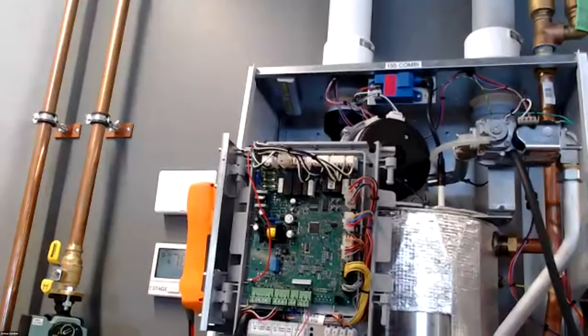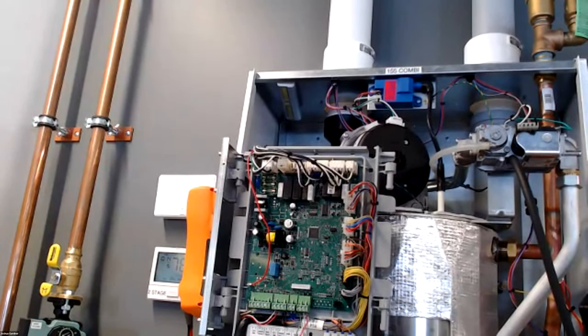And then on PVC, every 90 is 5 feet and every 45 is 3 feet. And I recommend using long sweep 90s. You can use regular 90s, but anything we can do to relieve the restriction is best. With CPVC, with poly, every 90 is 10 feet and every 45 is 5 feet. So we get a little bit more restriction there, but poly I think is a better way to go because it's essentially designed for exhaust, can handle higher stack temperatures.